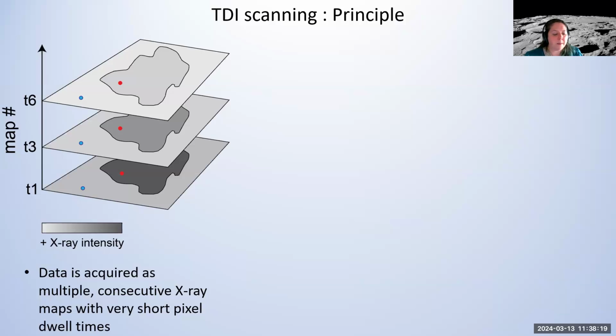Microprobes are very finely tuned, amazing beasts, and so usually our stage reproducibility allows us to do that even in stage mapping mode, where these repeat analyses have the same location for each pixel on the sample. And so we can look at the change in intensities over repeat beam exposure, and track any change in the samples.